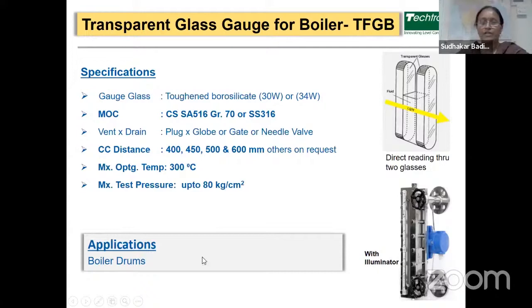Maximum operating temperature is up to 300 degrees Celsius and maximum test pressure up to 80 kg per centimeter square. The application is boiler drum. Here you can see on the right side the gauge with the illuminator. So here you can see the liquid level through the glass, which gives you the direct reading of liquid level.